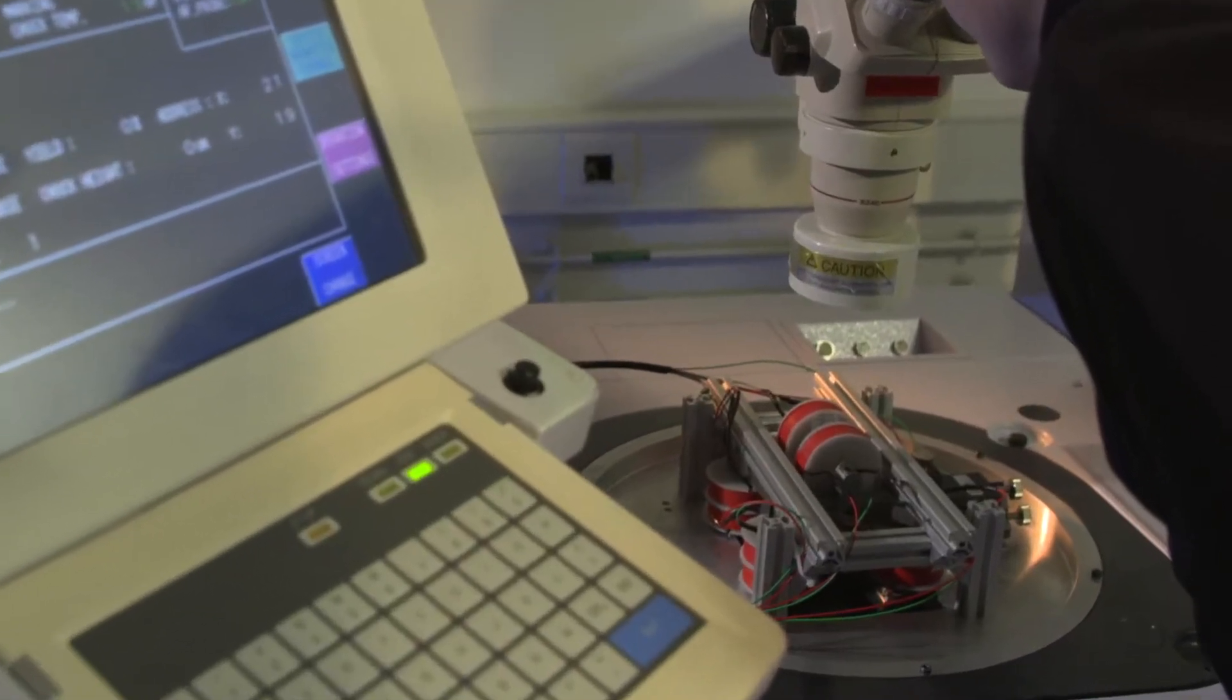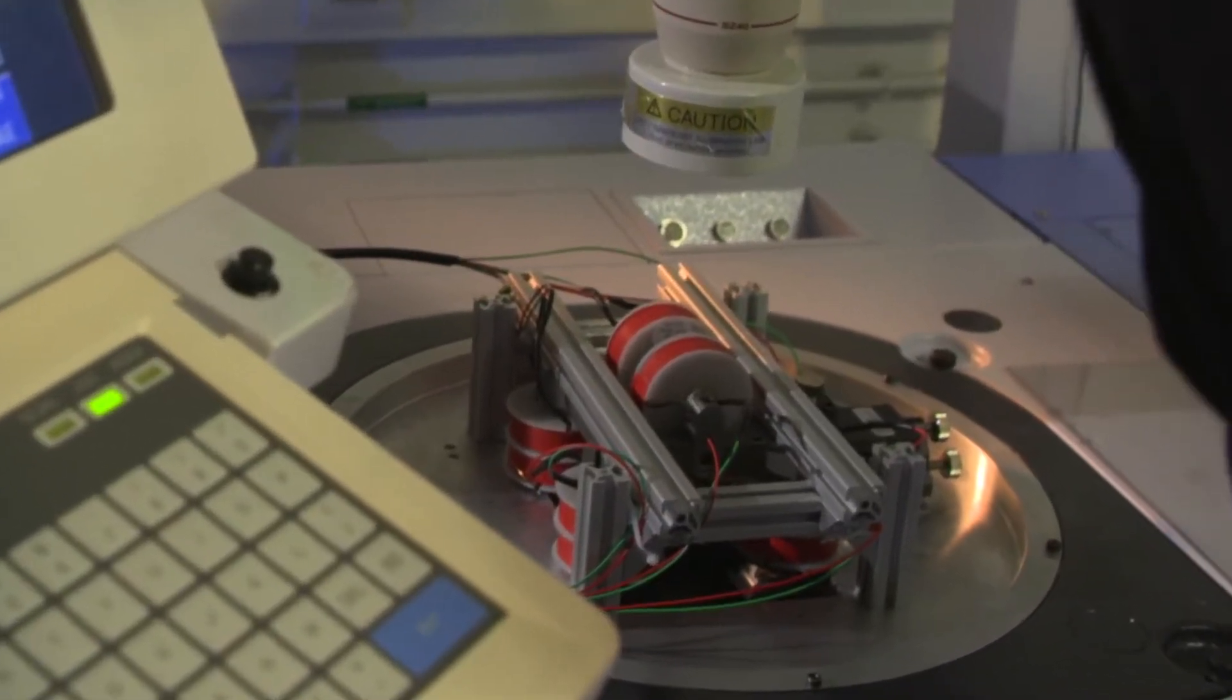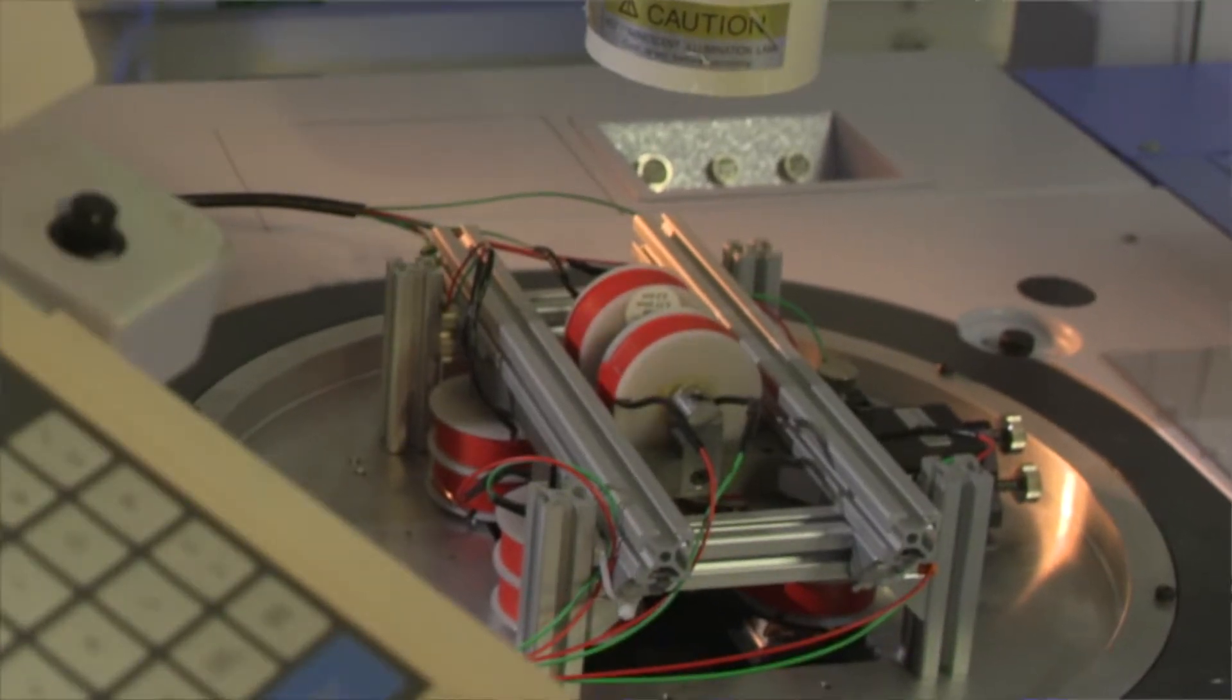The way the tester works is that we are monitoring the resistance of a magnetic tunnel junction while we are sweeping a magnetic field.